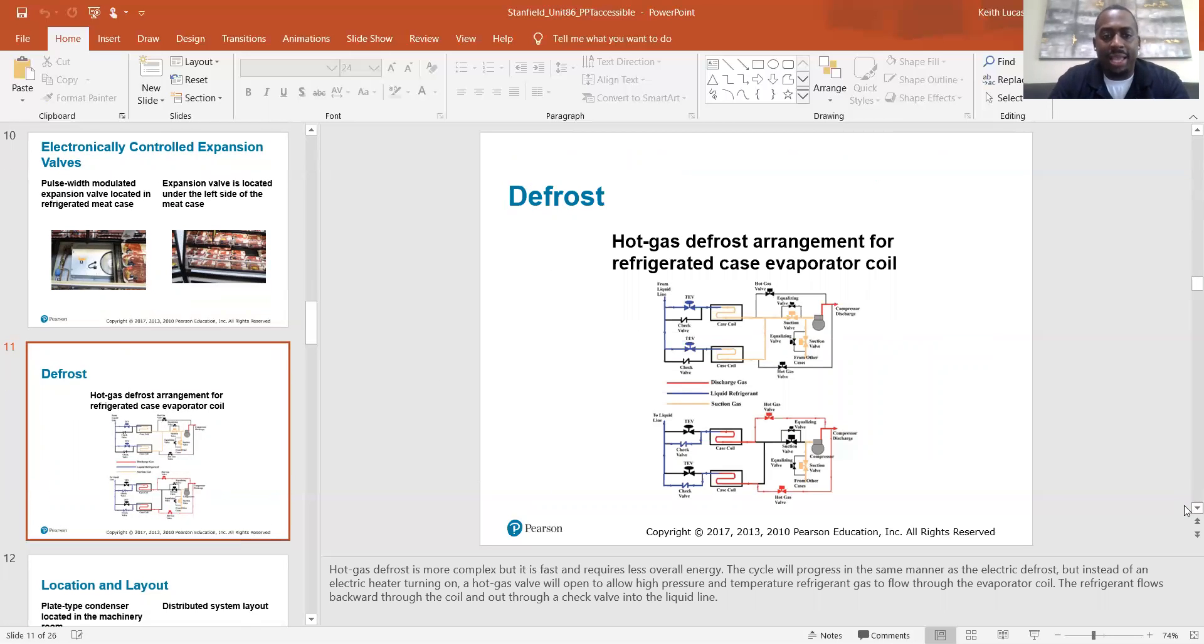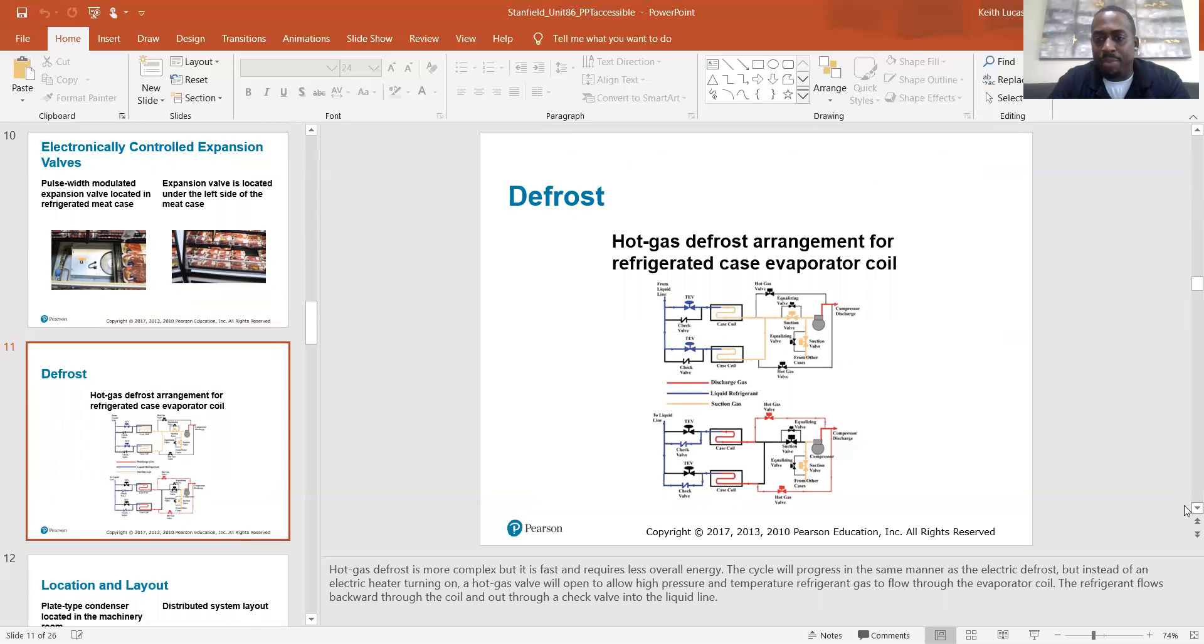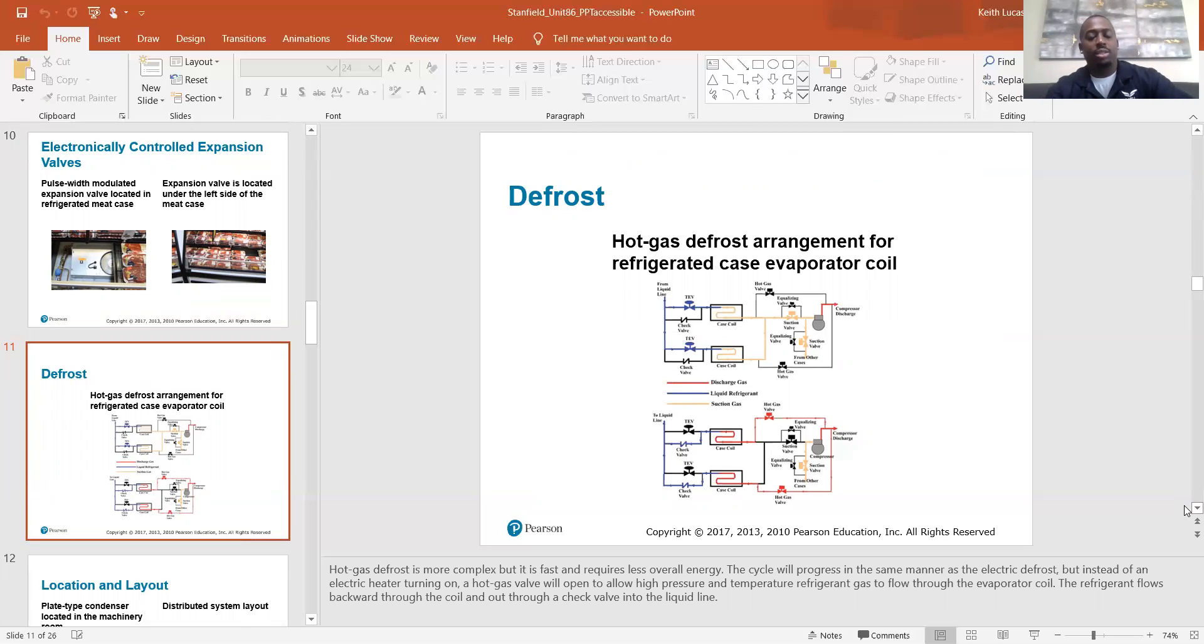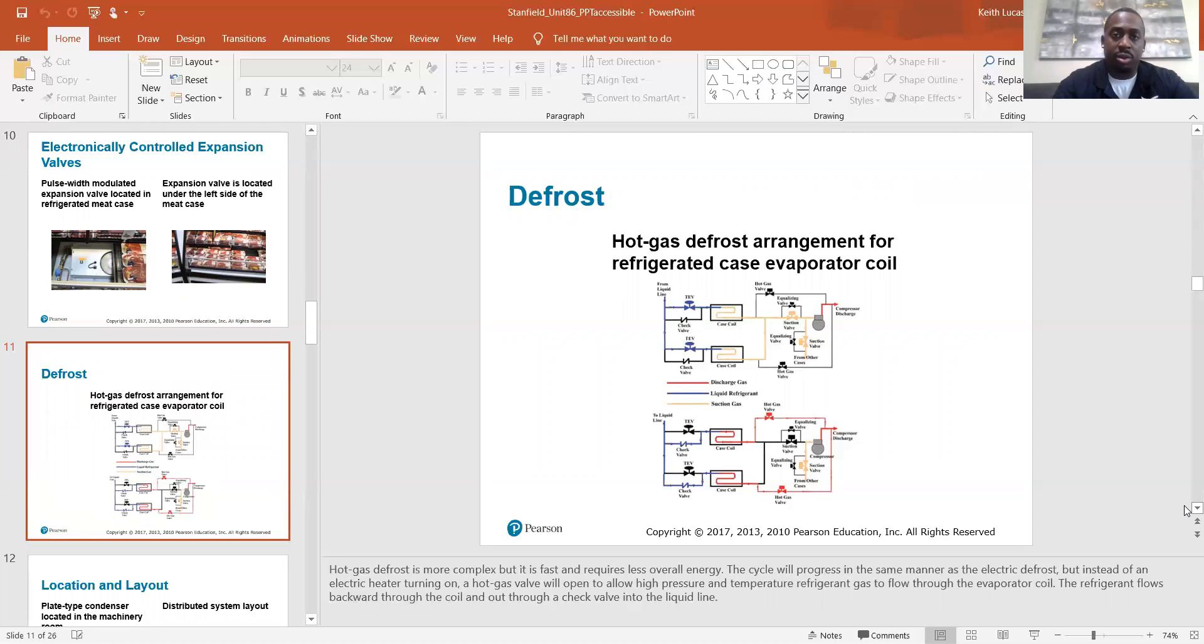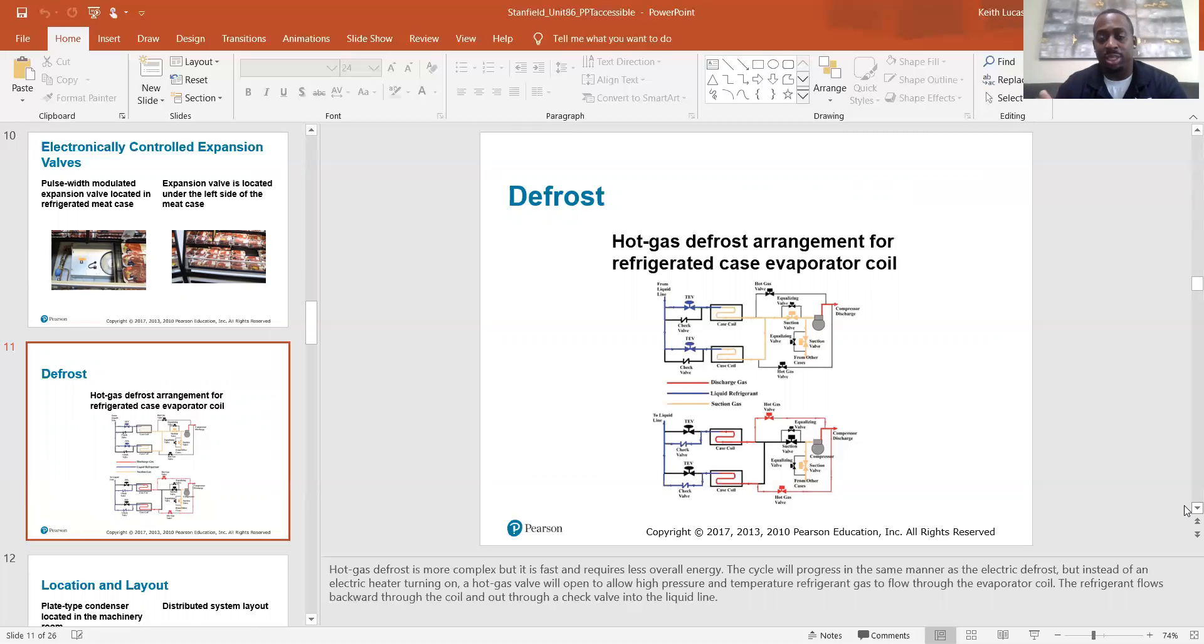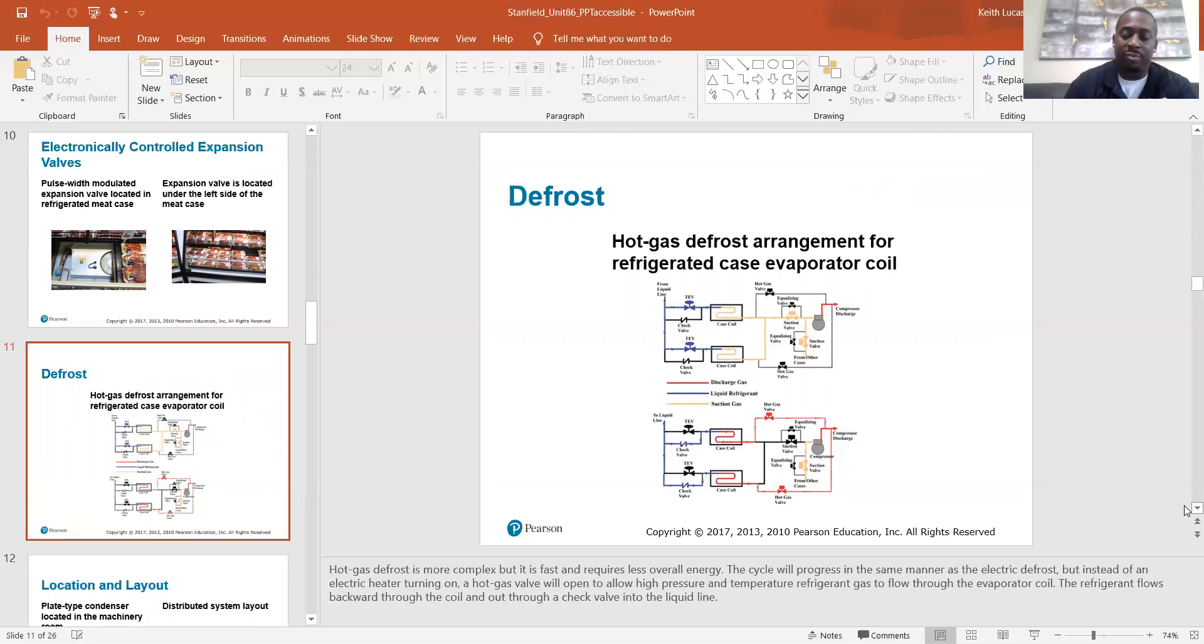Defrost. Hot gas defrost is more complex, but it is fast and requires less overall energy. The cycle will progress in the same manner as the electric defrost, but instead of an electric heater turning on a hot gas valve will open to allow high pressure and temperature refrigerant gas to flow through the evaporator coil. The refrigerant flows backward through the coil and out through a check valve into the liquid line. So basically the discharge gas goes from your compressor straight to your condenser coil. But in the hot gas defrost cycle, there's a solenoid valve that'll open up and allow the hot gas, the discharge gas coming from the compressor to bypass the condenser coil and go straight to your evap coil to defrost the ice buildup.